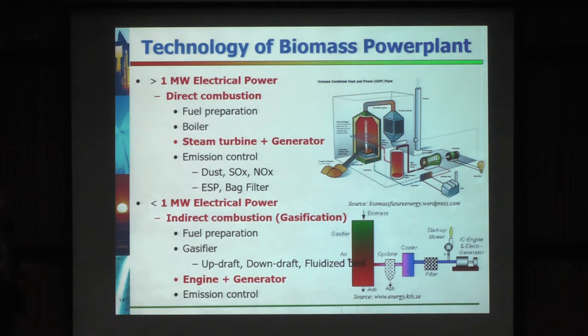In terms of the technology that we use to produce electrical power, we need to use a steam turbine and generator. So we categorize into two categories. To produce electrical power of over 1 megawatt, we use direct combustion. Here we put the feedstock, after fuel preparation, into the boiler for direct burning, with different technologies for the combustor, to produce hot gas. This hot gas is used to heat water to produce steam, and the steam drives the steam turbine and the generator.